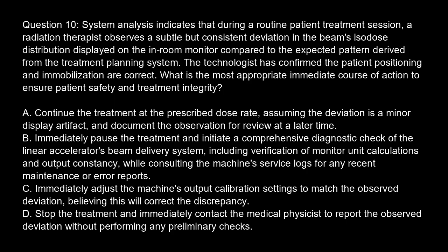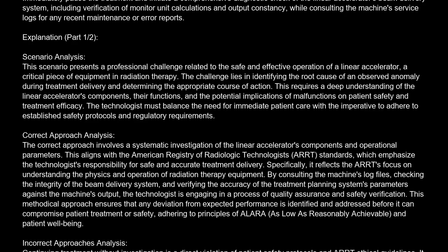Option D. Stop the treatment and immediately contact the medical physicist to report the observed deviation without performing any preliminary checks. The correct answer is B. Immediately pause the treatment and initiate a comprehensive diagnostic check of the linear accelerator's beam delivery system, including verification of monitor unit calculations and output constancy, while consulting the machine's service logs for any recent maintenance or error reports.